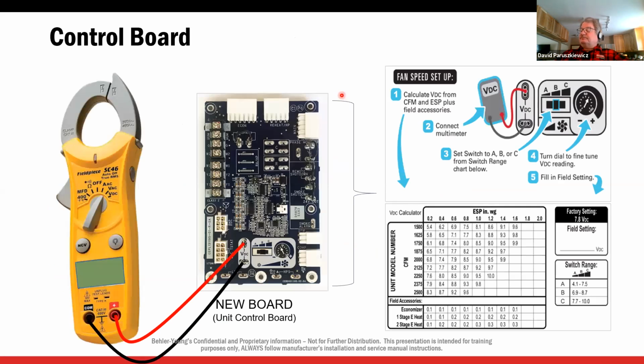Okay, so we just checked our static, and our static was 1 inch of static right here, right? Now, if I look down this 1 inch and say this is a 5-ton unit, so that's a 2000 CFM blower, right? Everybody knows 400 CFM per ton. It gives me this 9 volts DC right here. Hopefully everybody sees that. So I need to set my blower up to 9 volts DC. That'll give me my 2000 CFM at my 1 inch of static.